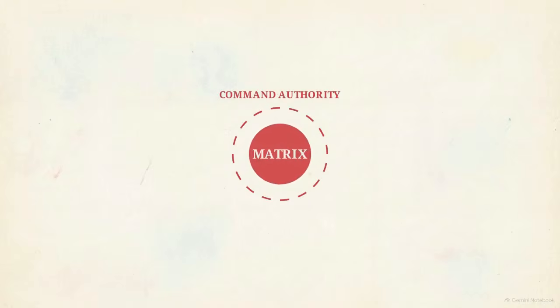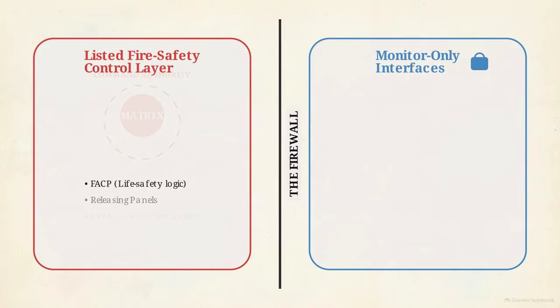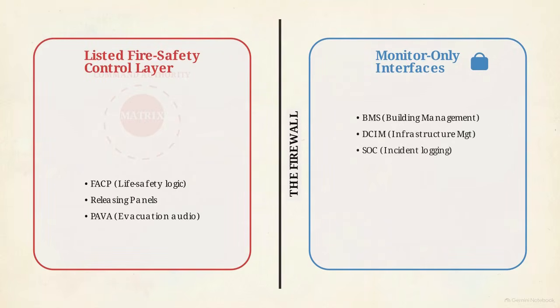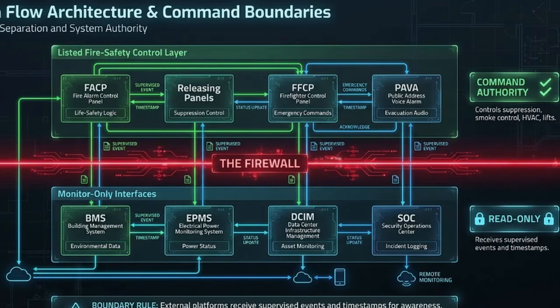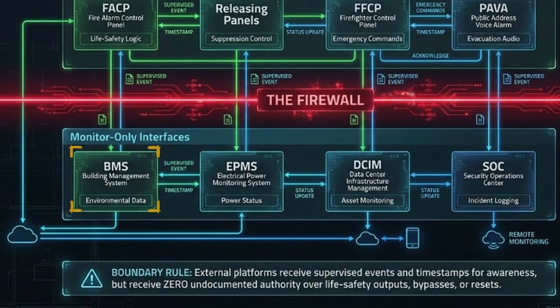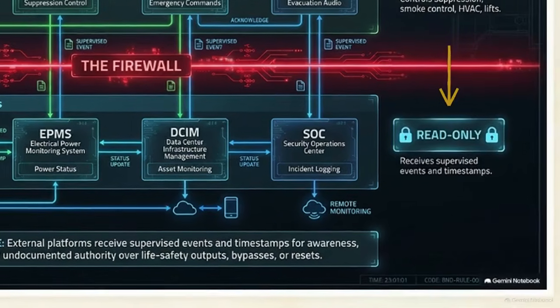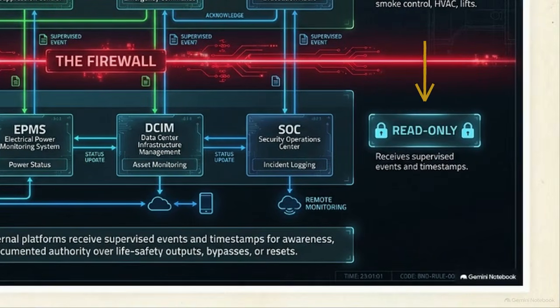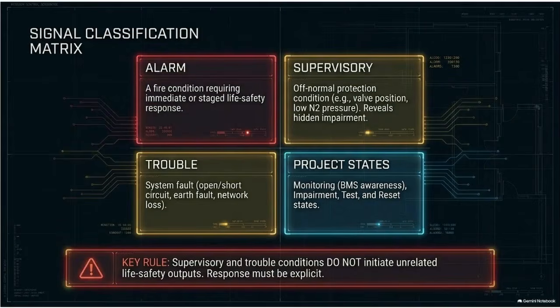To maintain the integrity of that matrix, the facility must physically and digitally isolate the systems that execute life safety commands from the systems used for general facility monitoring. This data flow architecture illustrates isolation. A red firewall separates the fire safety control layer from monitor-only interfaces like the building management system below. Lower-tier platforms receive supervised events for awareness, but hold absolutely zero undocumented authority to trigger life safety outputs, bypasses, or resets. This signal classification matrix enforces that rule, distinguishing an alarm condition from a supervisory condition.